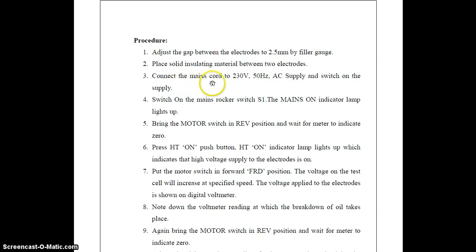Connect the main cord to the 230 volt 50 Hz AC supply and switch on the supply. Then switch on the main rocker switch S1. The mains is on, then the indicator lamp lights up. Then bring the motor switch to the reverse position and wait for the meter to indicate 0, meaning the meter reading should be 0. Then press the high tension on push button. Then HT is on. The indicator lamp lights up, which indicates the high voltage supply to the electrode is on. Then put the motor switch in the forward position.